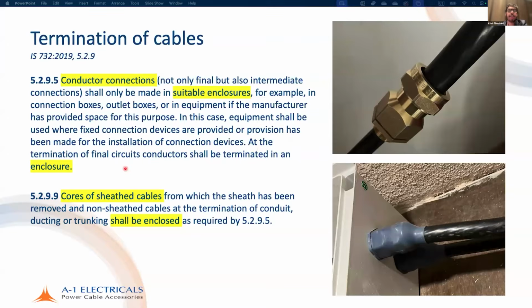Importantly, at the termination of final circuits, conductors shall be terminated at enclosures. Extremely important, because when a cable enters an enclosure, this termination has to be made in a correct manner. What is this correct manner? There's further information provided. Cores of sheathed cable. A sheathed cable is, for example, a multi-core cable. There's insulation on the individual copper or aluminum conductors, and an overall oversheath.